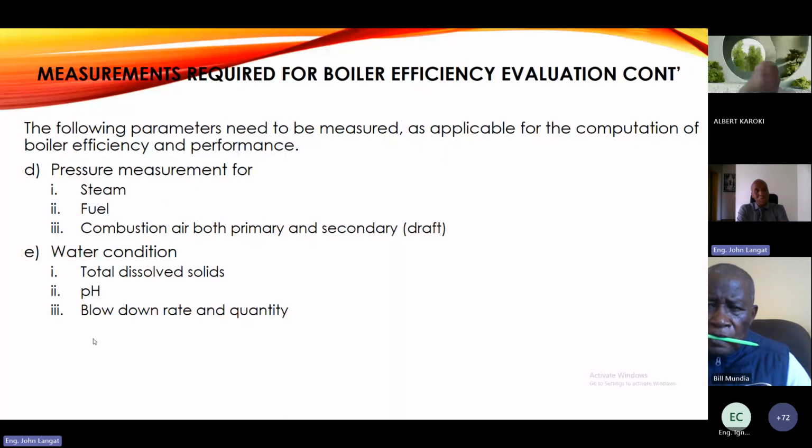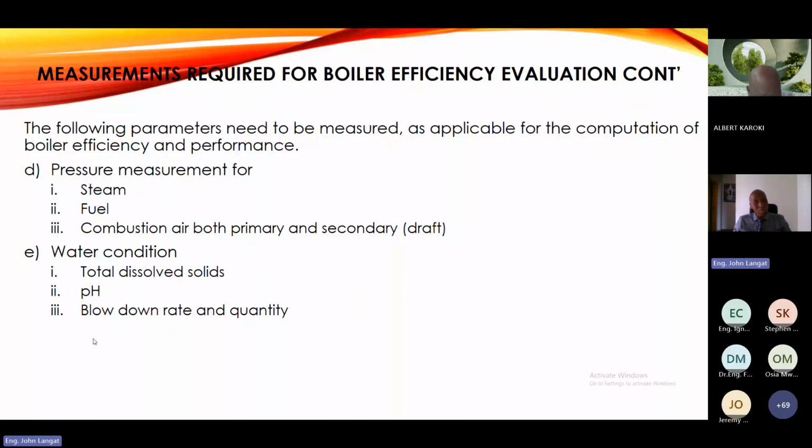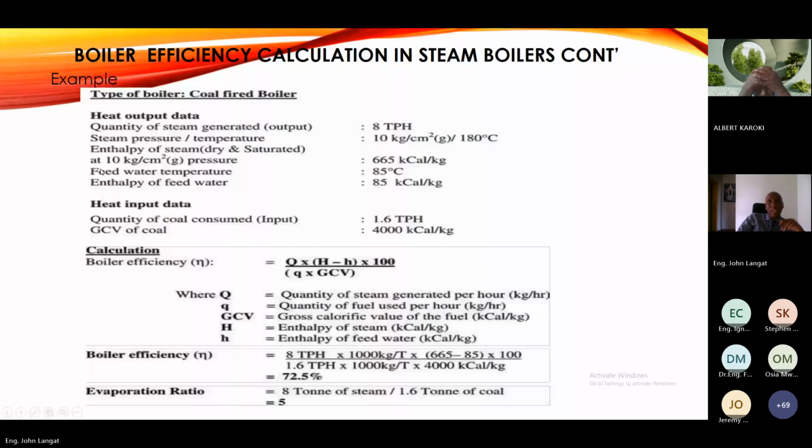And you see the rate of blowdown. If you do 3 blowdowns, you are talking about either 6 to 7 cubic meters of firewood. So if you reduce it to 1 or even none, because you've treated your water, then it's closed loop, then it might be good to go and save a lot of energy. Those are recommendations you need to make.